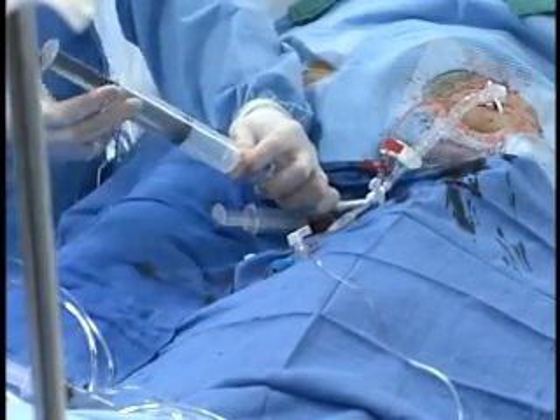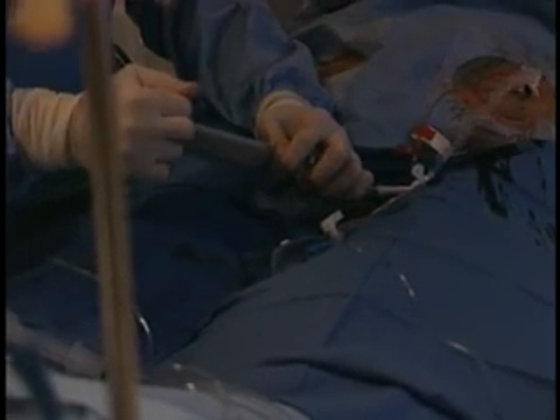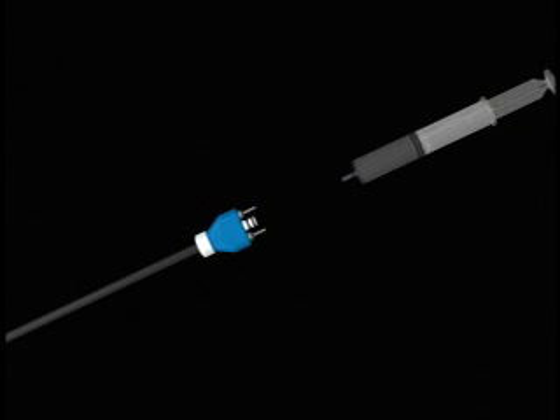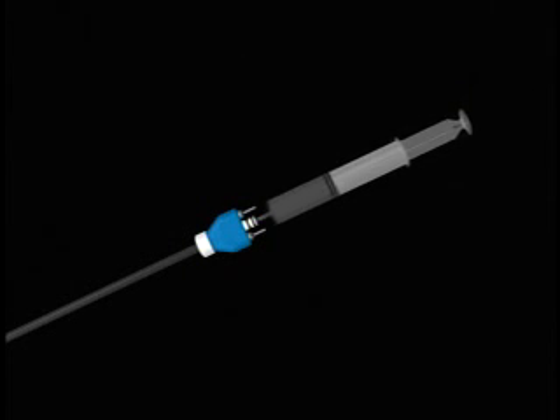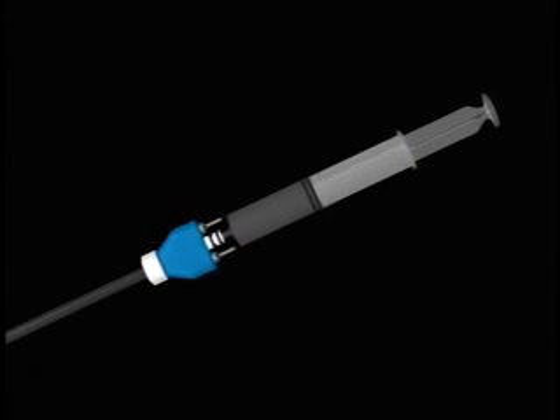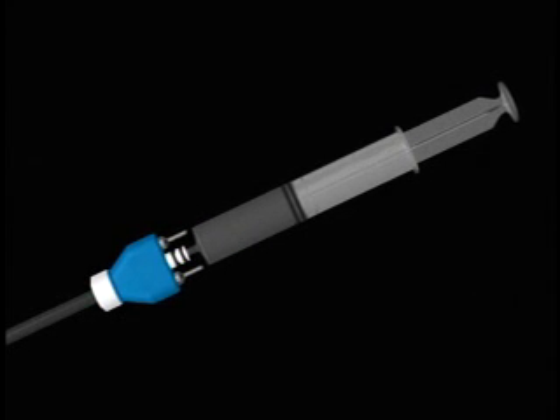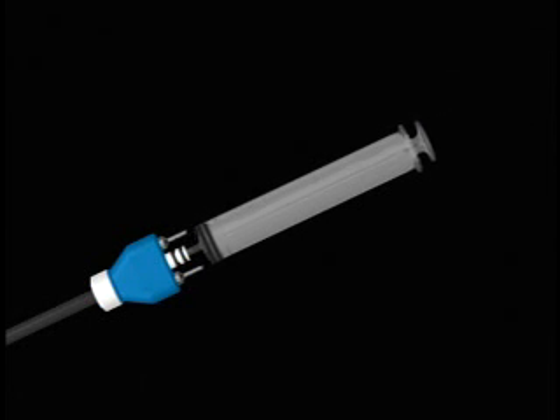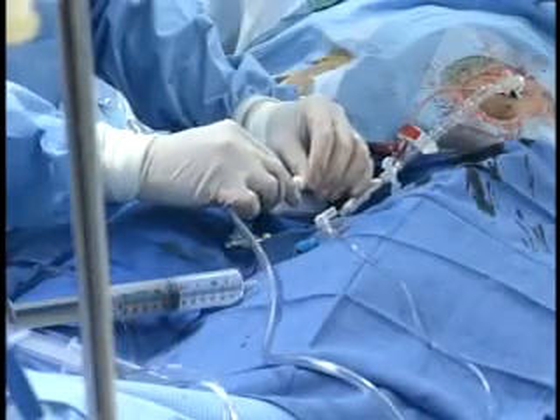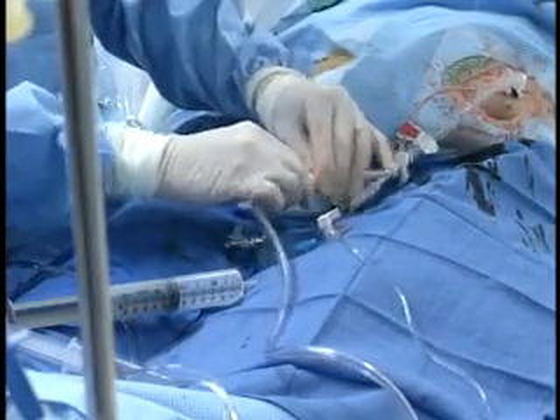Withdraw and confirm no blood is present. Using 30 to 40 cc's of air, gently inflate and deflate the IAB manually. Alternately, manual inflation may also be performed by removing the color-coded connector from the console, attaching the syringe to the middle port, gently withdrawing to confirm no blood is present in the gas line, and gently inflating. Reattach to console and resume pumping.